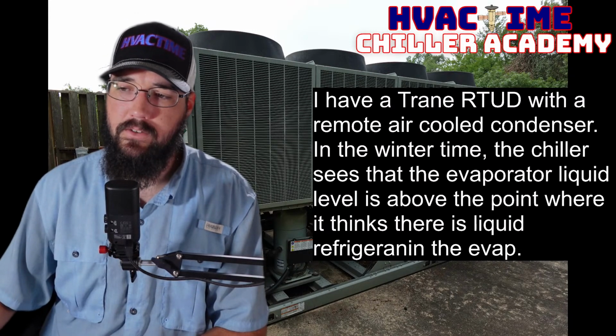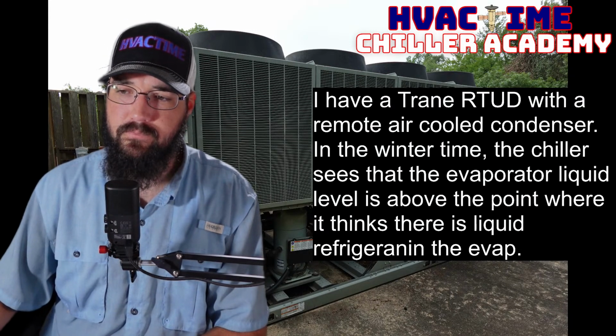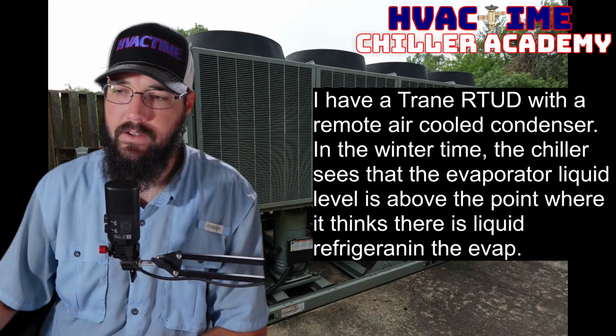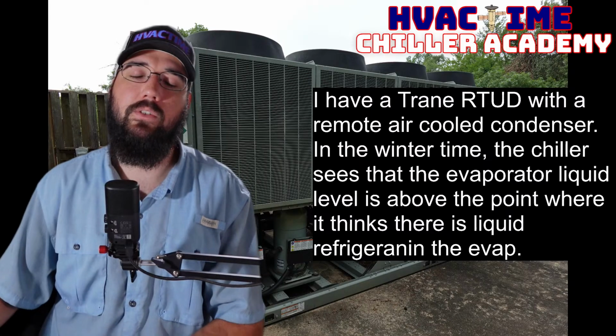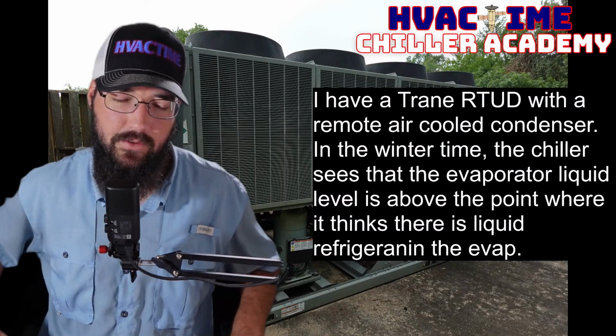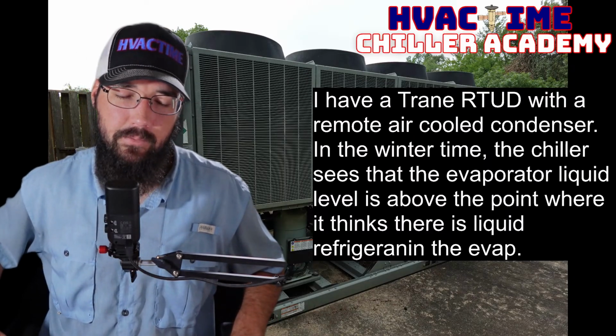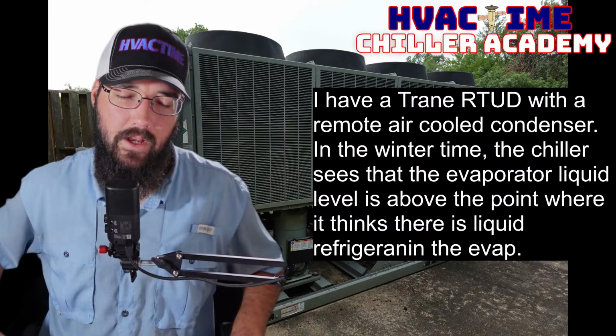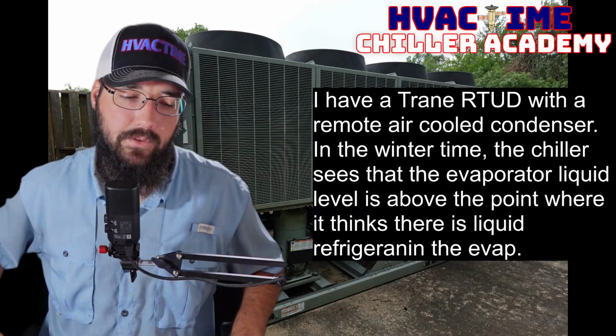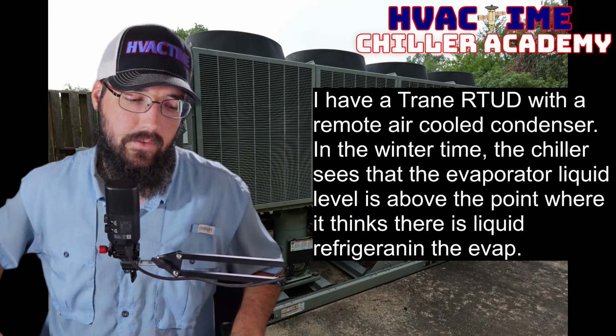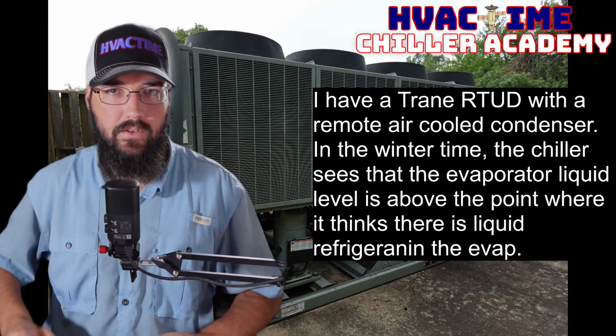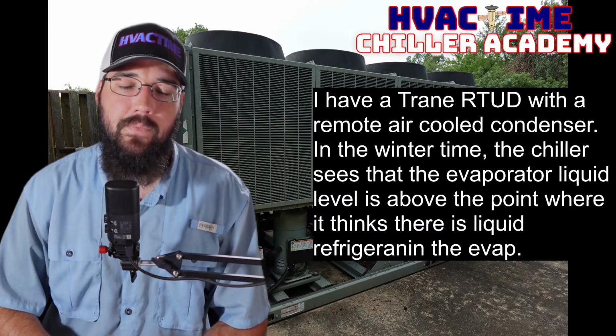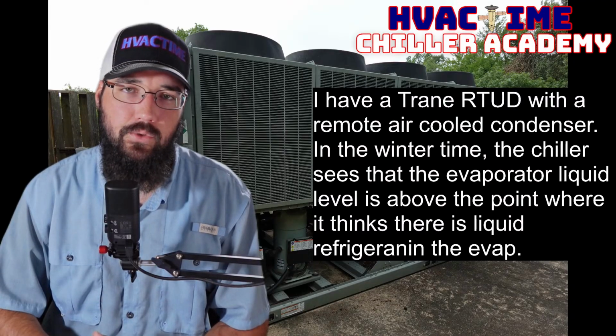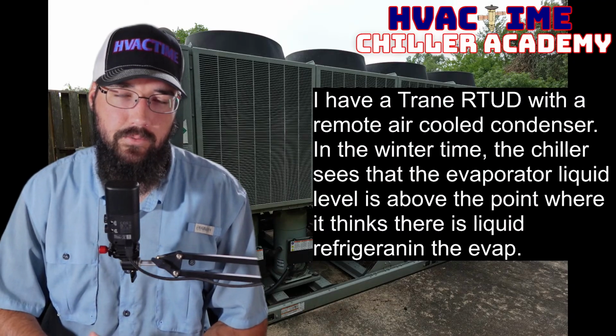So I get that it's pumping down. I'm trying to understand, and it sees the high refrigerant level after. Okay, so it's okay. All right, now I'm on the same page. So after the pump down cycle, it's seeing high refrigerant levels. I would say that if the sensor itself is not sticking, then it is likely due to oil migration issues.